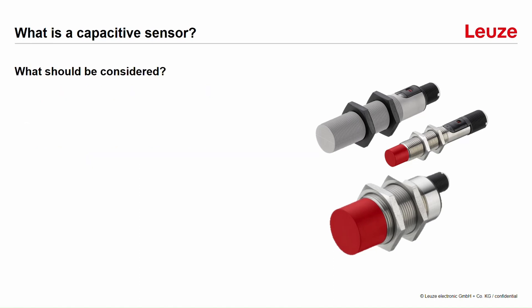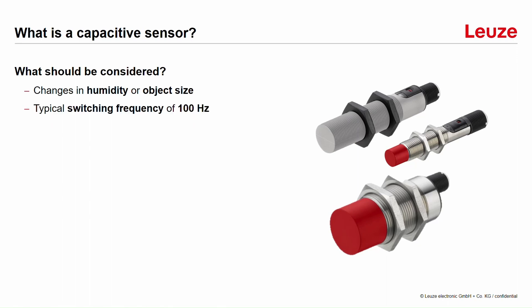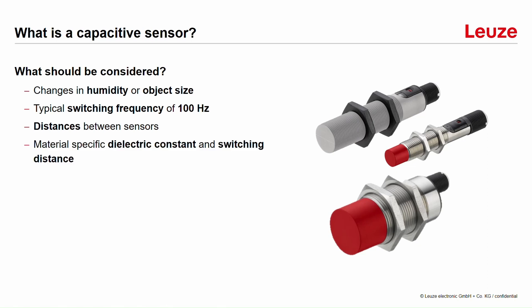What should be considered when you are using a capacitive sensor? First of all, you need to consider that there may be changes in the humidity or the size of the objects you want to detect. Besides, there are typical switching frequencies that have to be considered. You also need to care about the distances between the sensors. And a very important point is the switching distance and the material-specific dielectric constant — but what this means will be explained later.